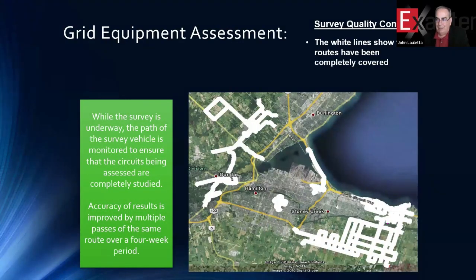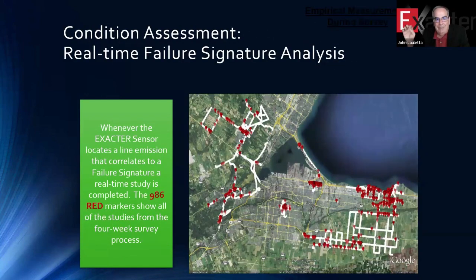So the way we would approach a problem would be to be called in to a utility where problems exist, and we would put our sensor in vehicles and drive around the circuits. And this shows a survey that was done at an actual utility, and you can see the white lines. They're where the survey vehicle ran. We're listening to VHF radio emissions, so it doesn't matter how fast the vehicle is traveling. It just travels at posted speed limits and so on. And then every time the signature of a partial discharge occurs and is detected, the sensor marks the location using GPS technology. And you can see there's a lot of problems here, 1,000.